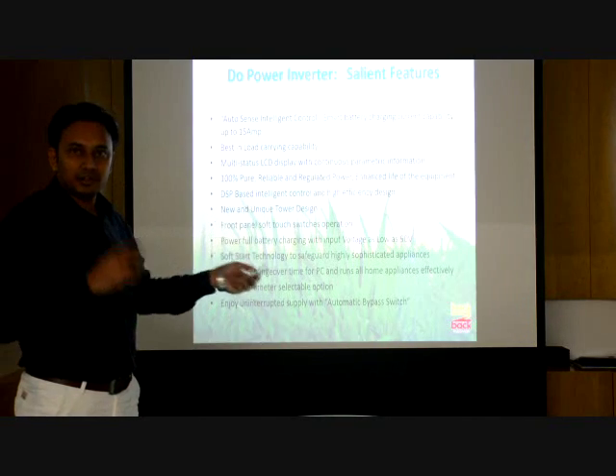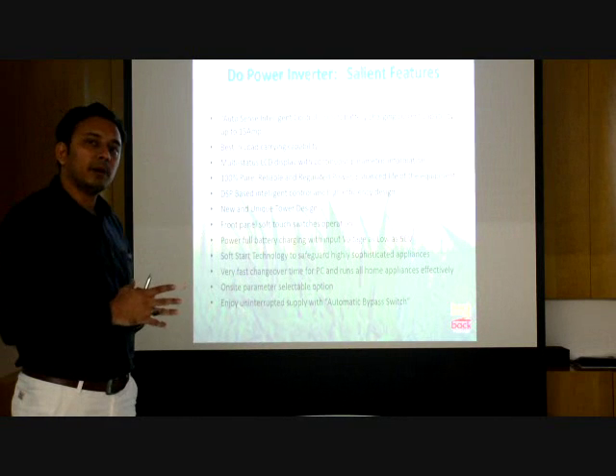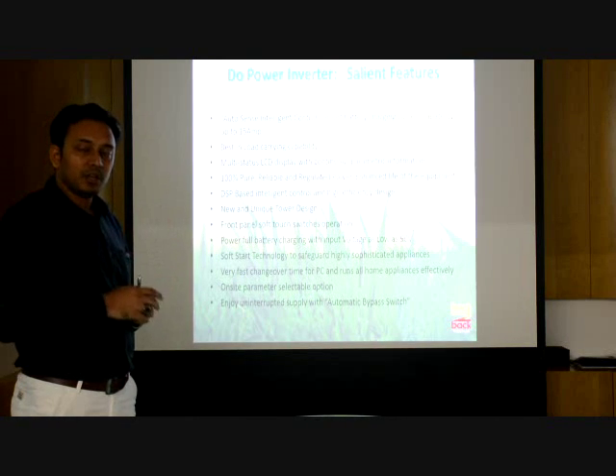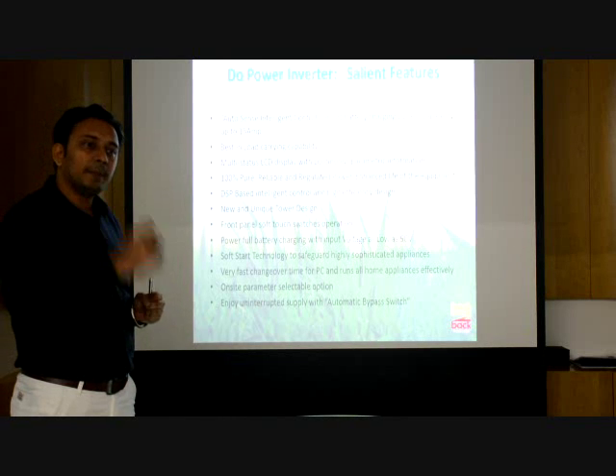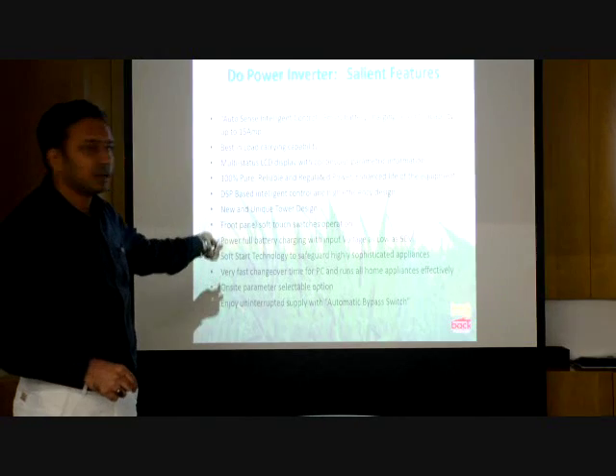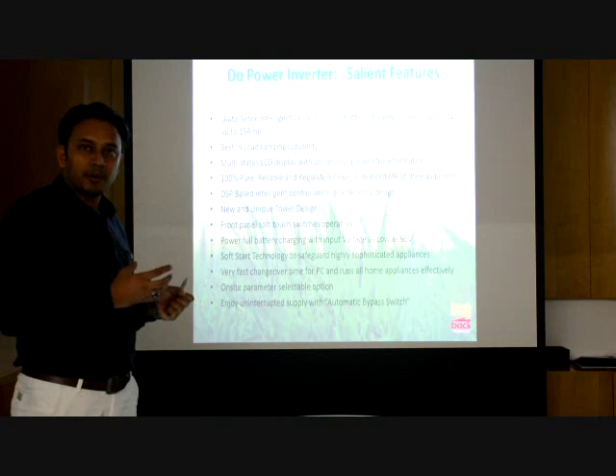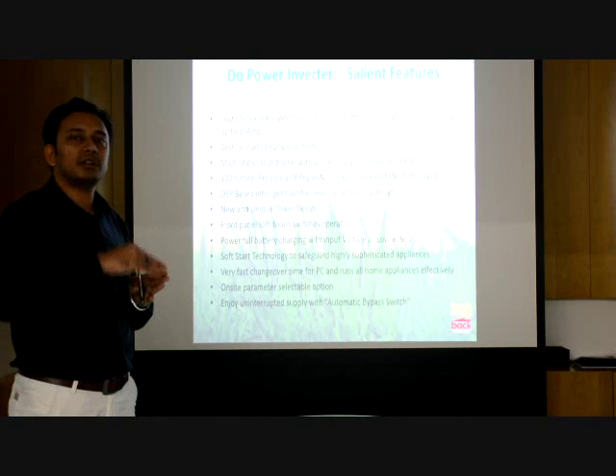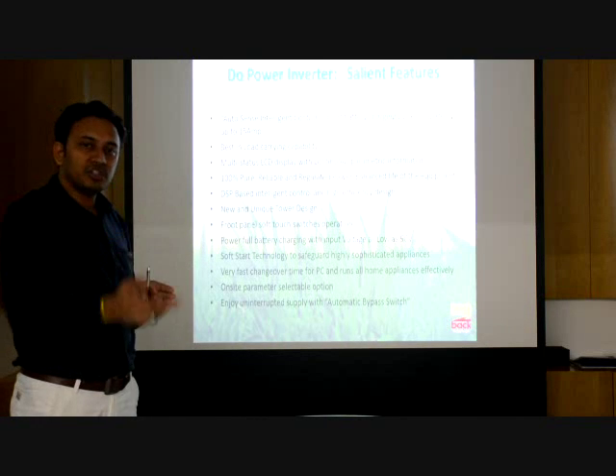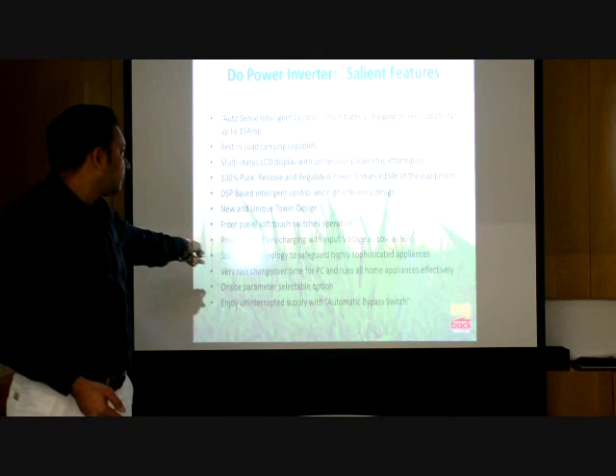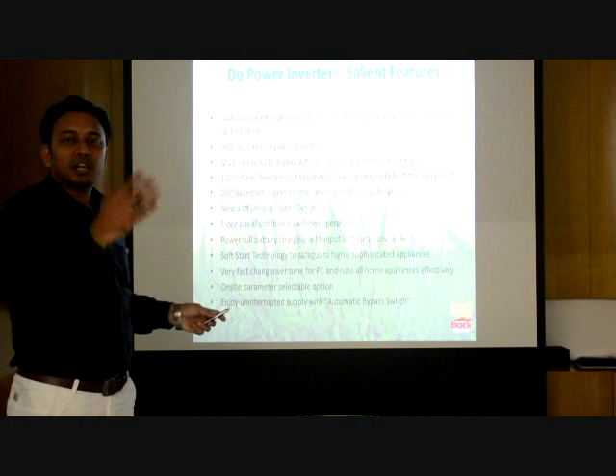Soft start technology means even if you don't have power coming from the government, but you have power already stored in your battery, you can start the application directly from battery mode. Other inverters will not start this way because they aren't equipped to take that much power from the battery initially - they're only equipped for the technology of running on the grid and then switching over. But this unit can take the load initially from soft start technology without grid power, taking it immediately from the battery itself.